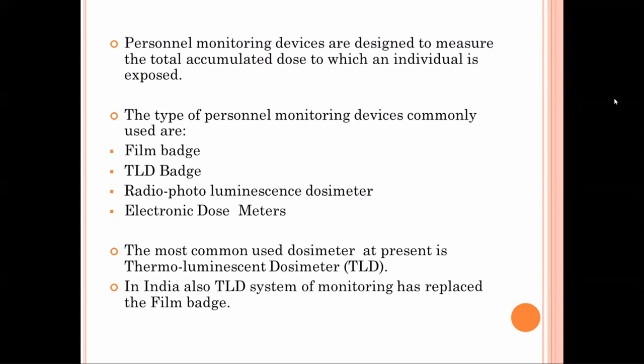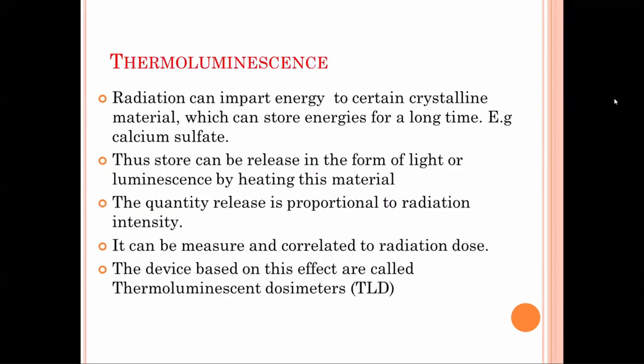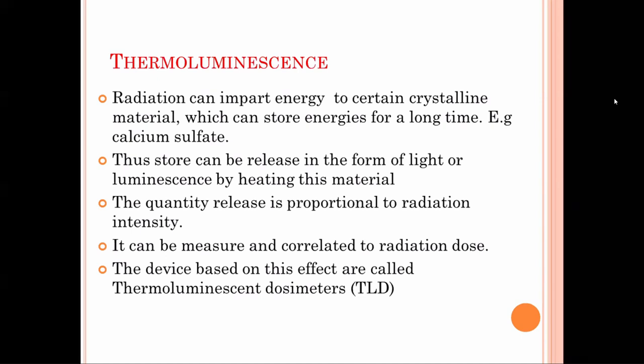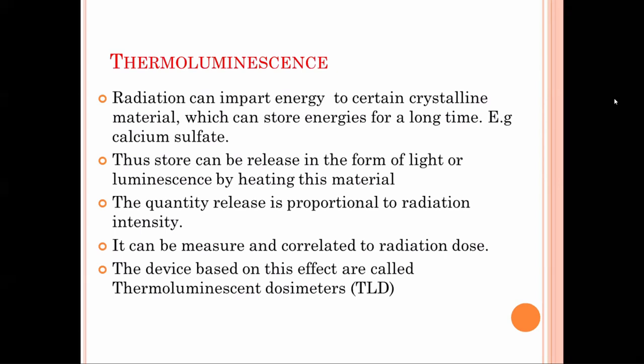Radiation can impart its energy to certain crystalline material which can store this energy for a long duration. In TLD, calcium sulfate material is used, and the stored energy can be released in the form of light emission after heating this material. During processing, we heat this material to about 300 degrees Celsius. The quantity of light released is proportional to the radiation intensity.